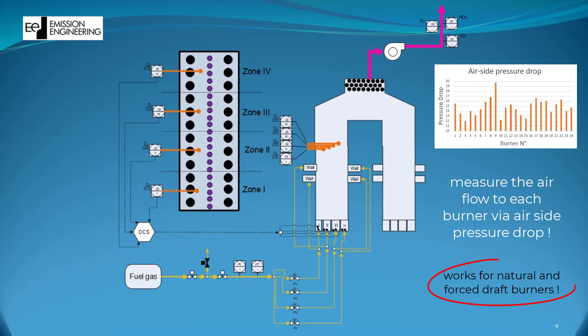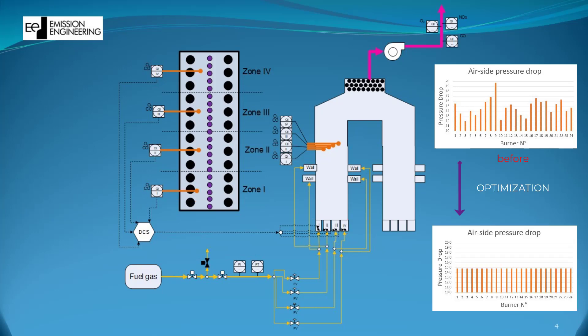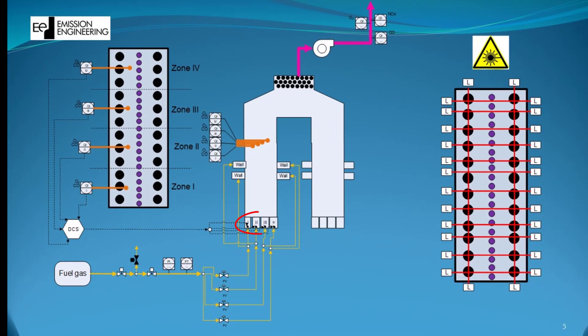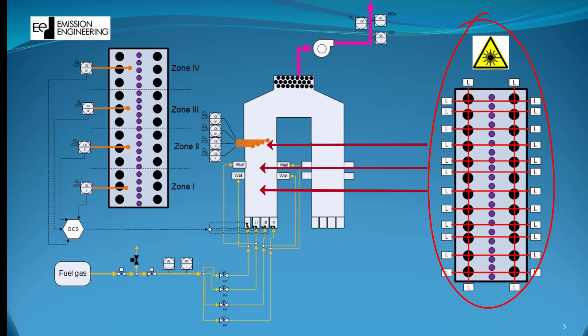With this approach, even on a complex furnace setup, the floor burners can be operated at, for example, 10% excess air, even without a specific O2 measurement capturing the O2 in the flue gas from the floor burners only — even if the burners in section 1 are on lower heat release than those in sections 2, 3, or 4. Other approaches, such as laser-based O2 and/or CO measurements, require two or even more levels of laser grids to really determine the effects of each individual burner. In practice, this is very costly to install and maintain, and cannot accommodate easy changes in furnace draft or wind conditions at the burner air inlets. Furthermore, the coils inside the combustion chamber may twist and move over time and can block the passage for the laser beams.